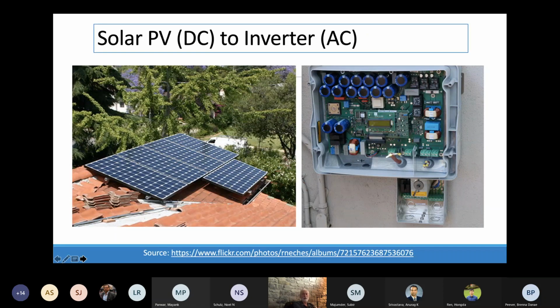Here is what a real small solar network might be. This one is not the greatest accomplishment in design given by the number of tiles that are standing around it. But typical solar photovoltaic roof mounted systems are a couple of kilowatts, no more than 4 kilowatt, and they are linked to small inverters like the one shown on the right. You see that inverter has a lot of capacitors, and those are the critical elements of what drives the lifetime of the system. So whereas solar panels can last easily 30 plus years, inverters rarely last more than half of that time, and they have to be replaced or substantially refurbished to continue their lifetime beyond that level.